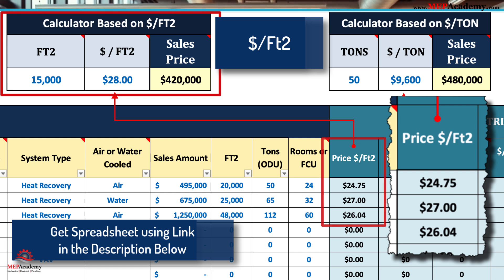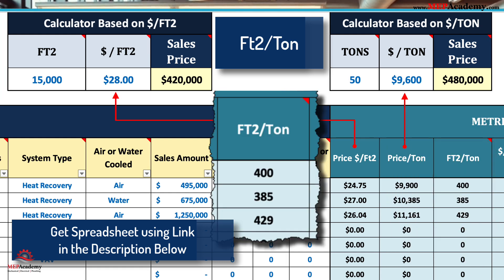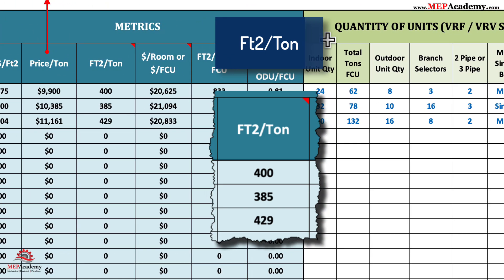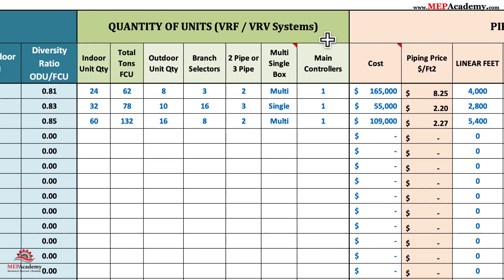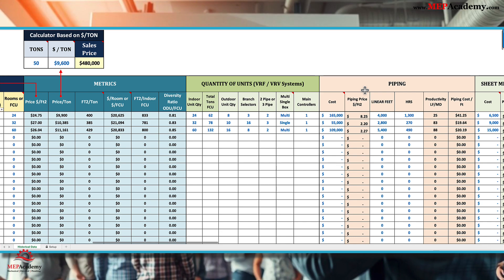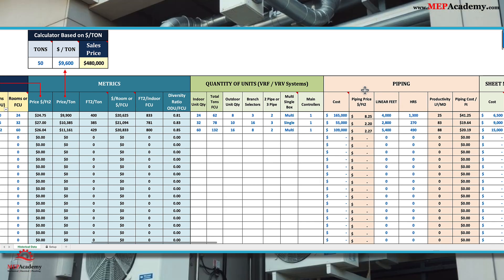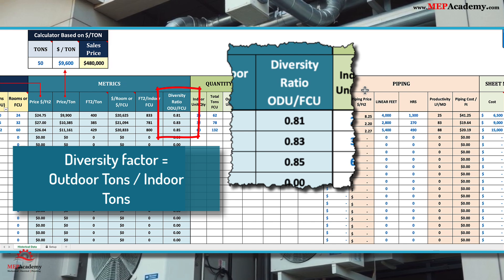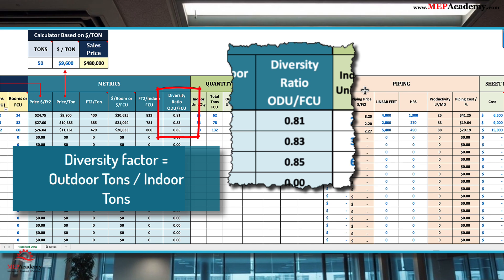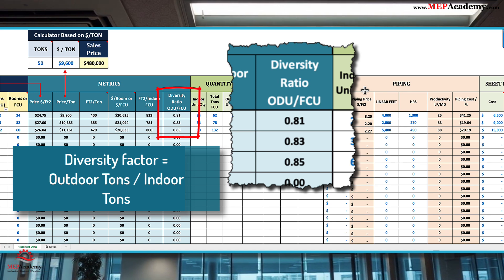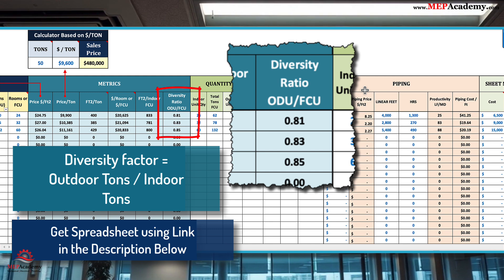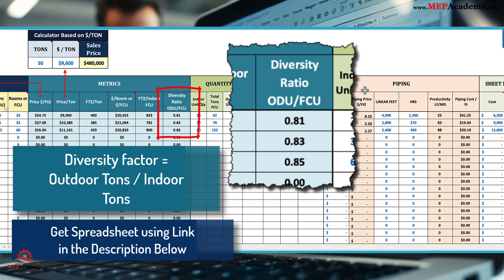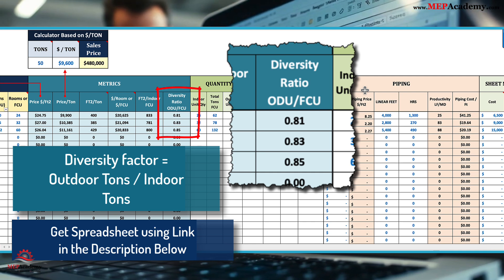2. Engineering metrics. Square feet per ton: optimize your system design by ensuring proper capacity allocation based on building requirements. Document all VRF design projects, whether VRF heat pump or heat recovery. This gives you a quick reference to how engineers size the system based on location and occupancy type. Diversity in HVAC systems refers to the ratio of the outdoor unit's capacity to the combined capacity of all connected indoor units, accounting for the fact that not all indoor units operate at full capacity simultaneously, as cooling or heating demands vary across spaces. This approach improves cost efficiency, reduces equipment size, and ensures energy savings without compromising performance.